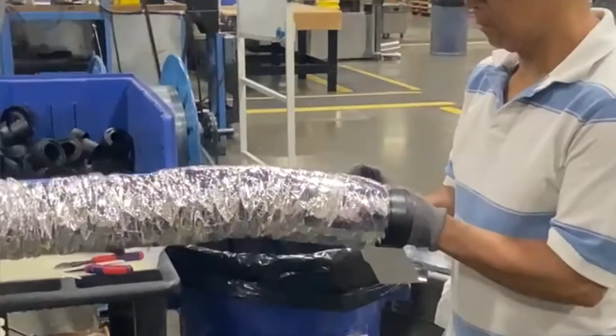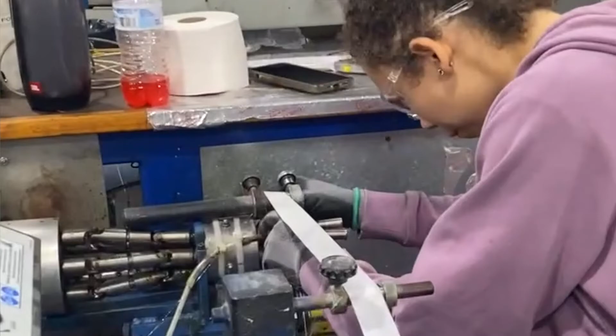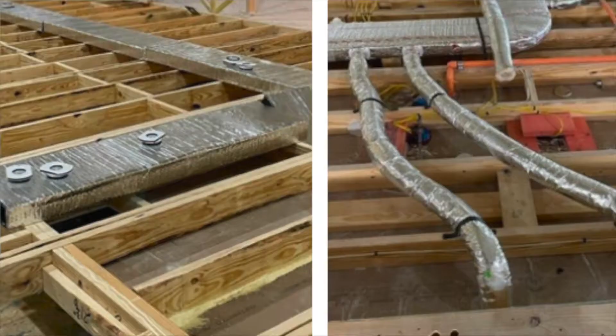And in a factory, typically, if we're working with the design and the engineer team, there's an interstitial that's usually at least 4 inches, sometimes 5, where we can use a rectangular duct that is 4 inches tall by 14, 4.5 by 15 when insulated. And what happens is, off of that flat duct in the interstitial between the floors, our small ducts run out. And so if it's a second floor coming onto the first floor module, all of the plenum, and typically the air handler is in the first floor.